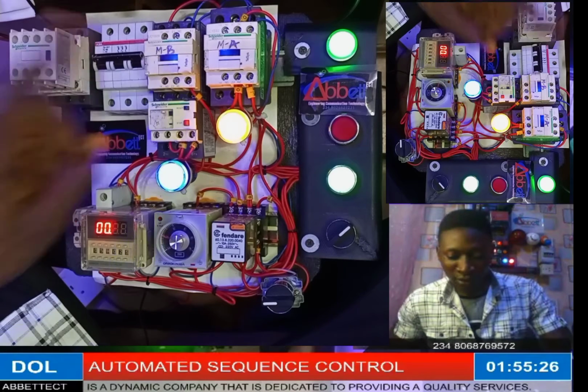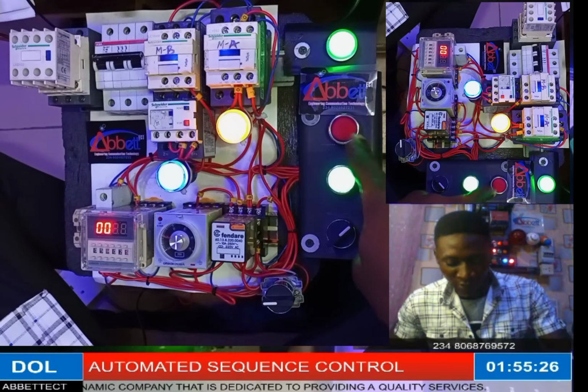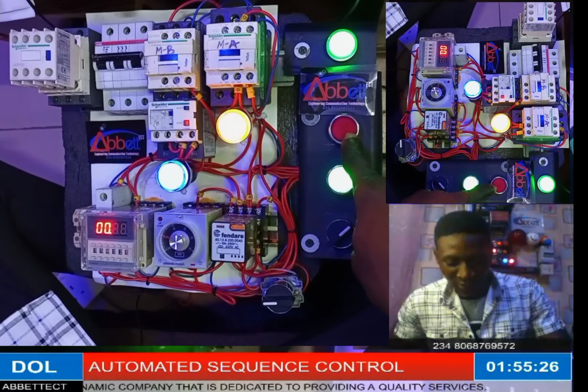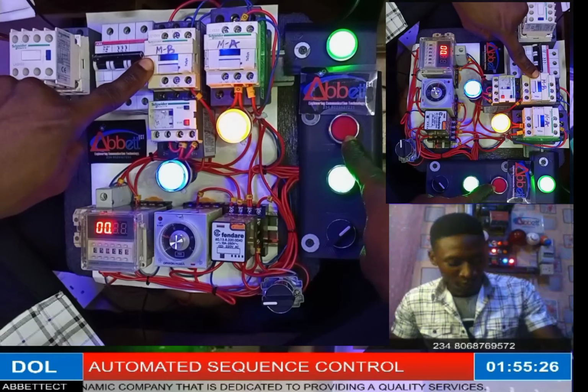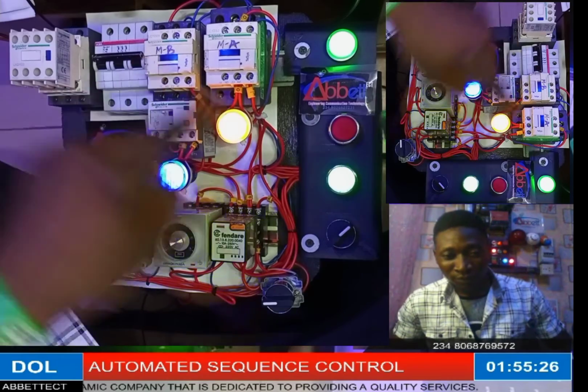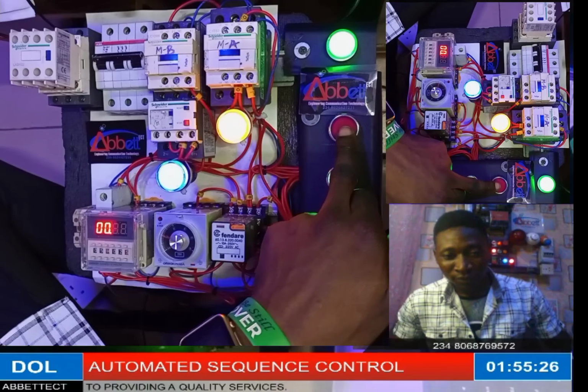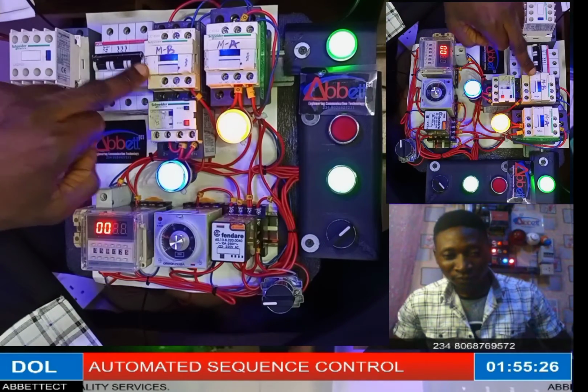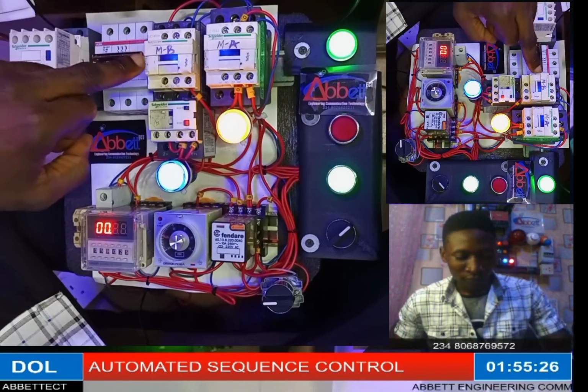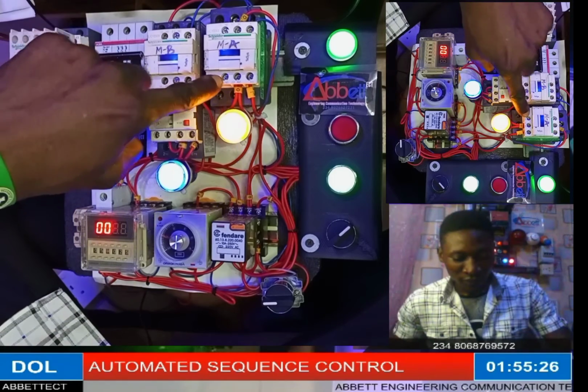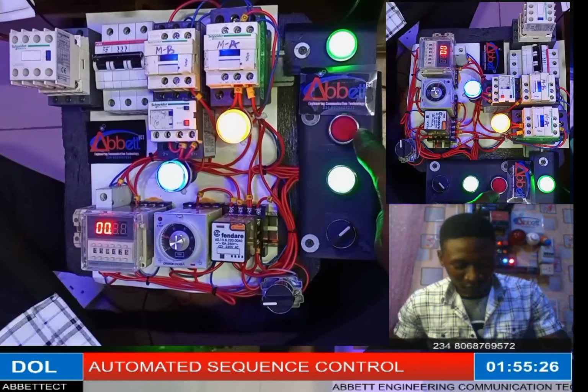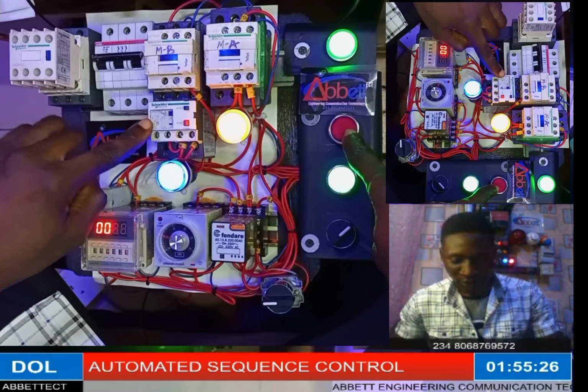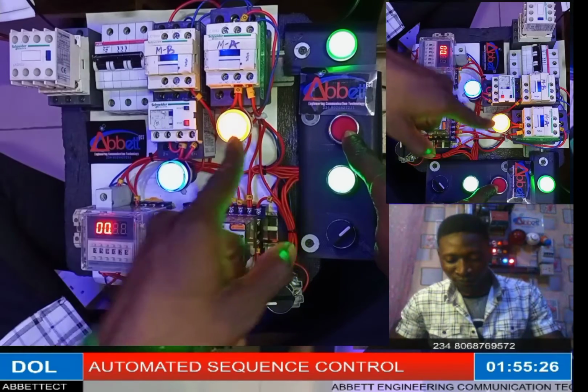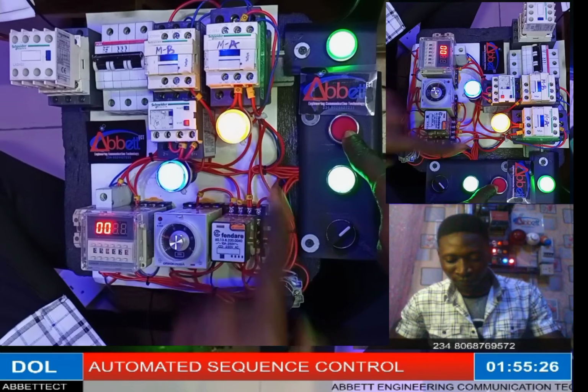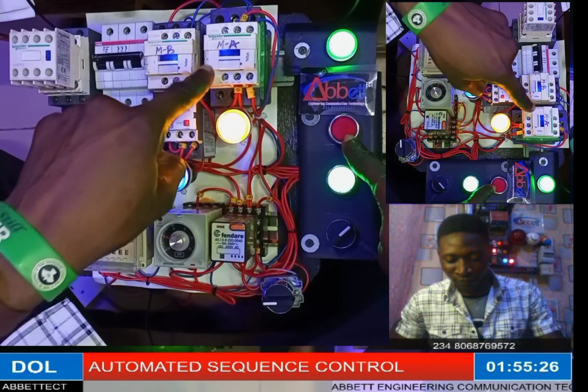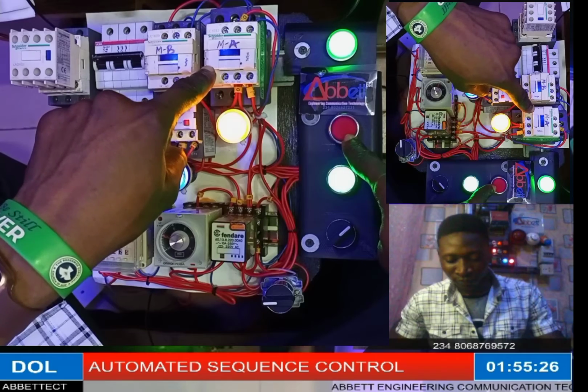Did you get it? So now, if I stop motor A, motor B will automatically stop. You understand? If I stop motor A, motor B will stop because the program says if motor A is not running, motor B will never run. So if I stop motor A now, motor B will automatically stop. But motor A itself will not stop immediately. It will wait for this stopper timer to dictate to this motor when to stop.